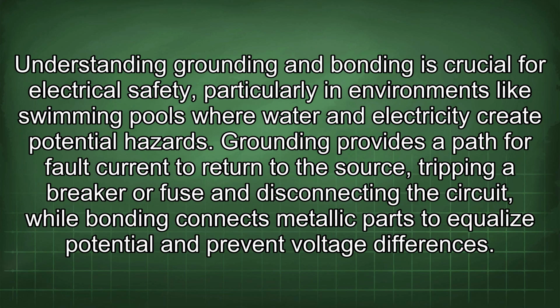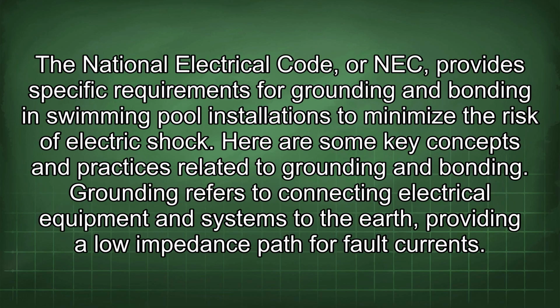Understanding grounding and bonding is crucial for electrical safety, particularly in environments like swimming pools where water and electricity create potential hazards. Grounding provides a path for fault current to return to the source, tripping a breaker or fuse and disconnecting the circuit, while bonding connects metallic parts to equalize potential and prevent voltage differences. The National Electrical Code, or NEC, provides specific requirements for grounding and bonding in swimming pool installations to minimize the risk of electric shock. Here are some key concepts and practices related to grounding and bonding.